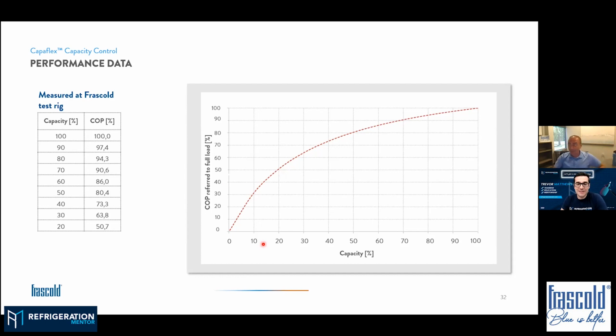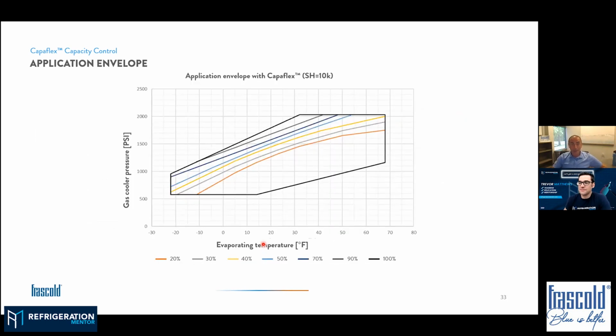Yes, correct. And of course, all the inefficiency we've seen is also translated into a limitation on the application envelope, because when we're talking about an inefficiency, we always get that inefficiency somewhere. In this case it would be on the isentropic efficiency of the compressor, which translates into a higher discharge temperature.